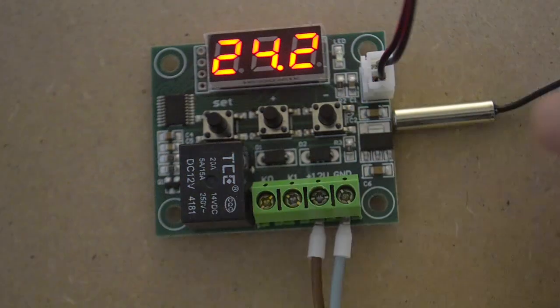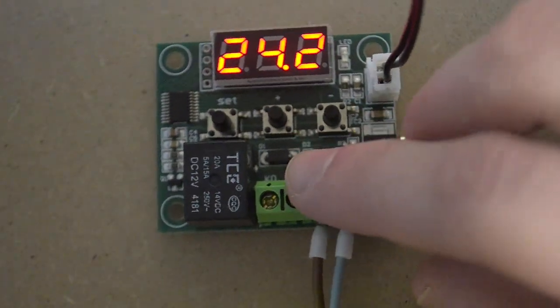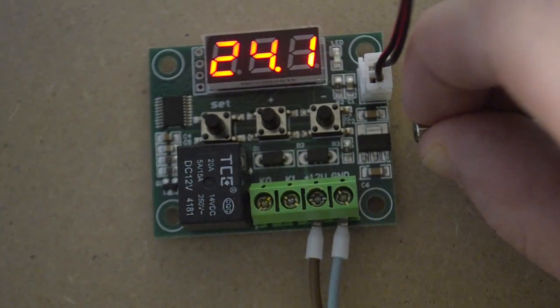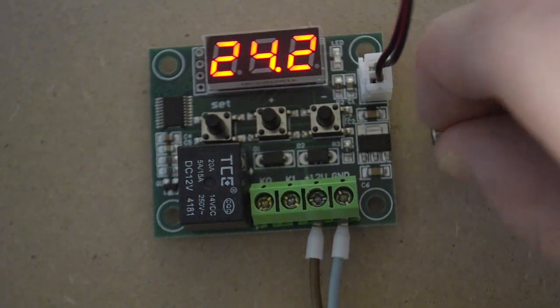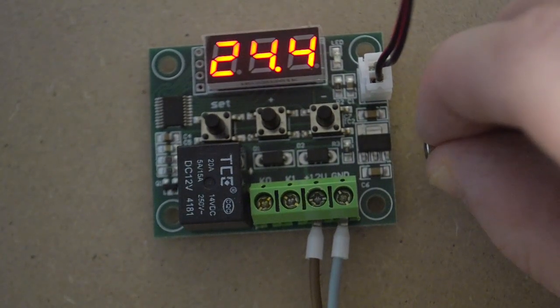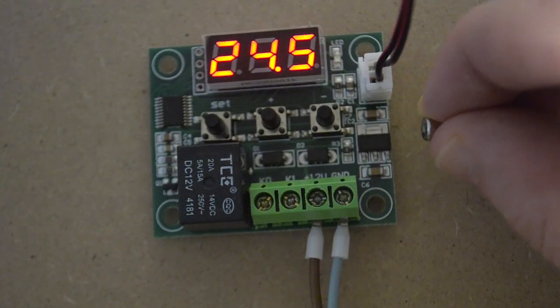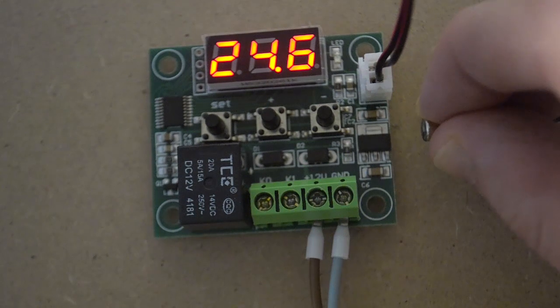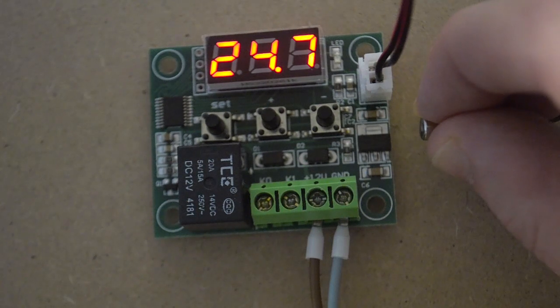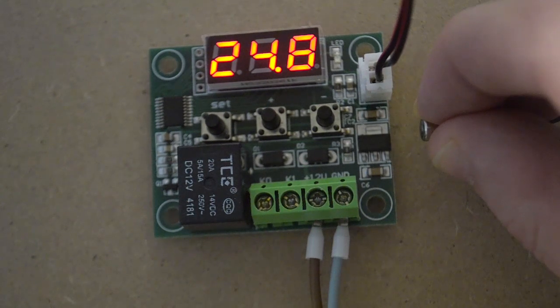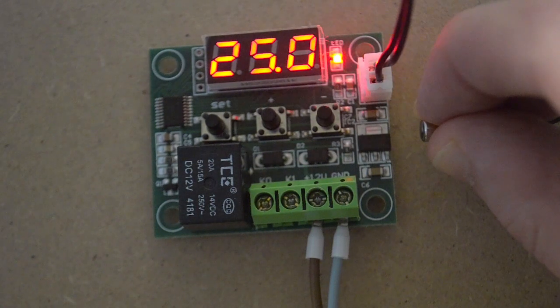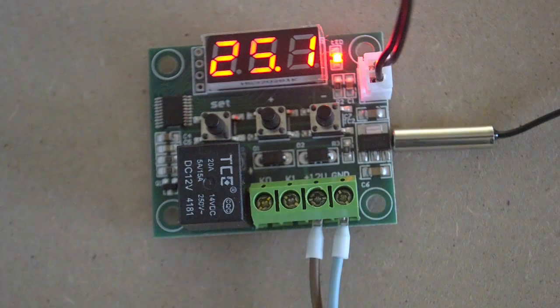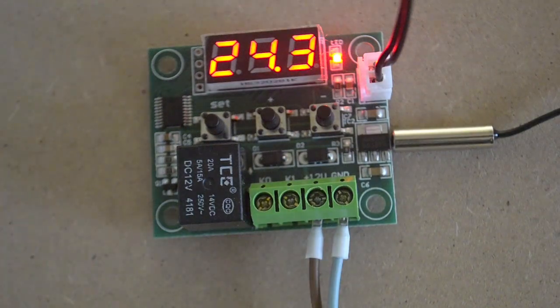Here's an example. The higher limit temperature is set to 25 degrees and the hysteresis range is set to 2 degrees. So the lower limit temperature is 25 minus 2 degrees, or 23 degrees.